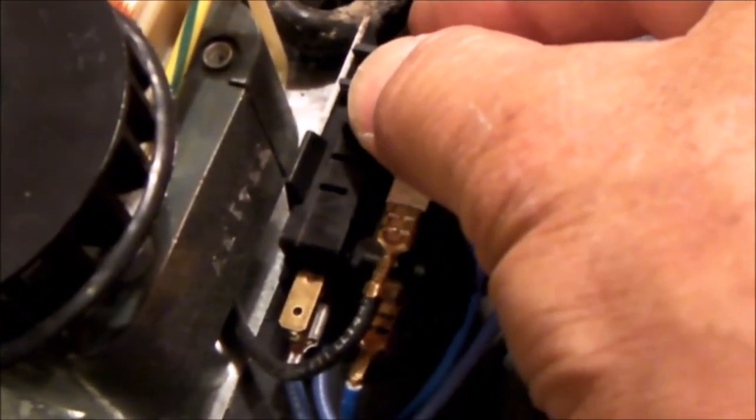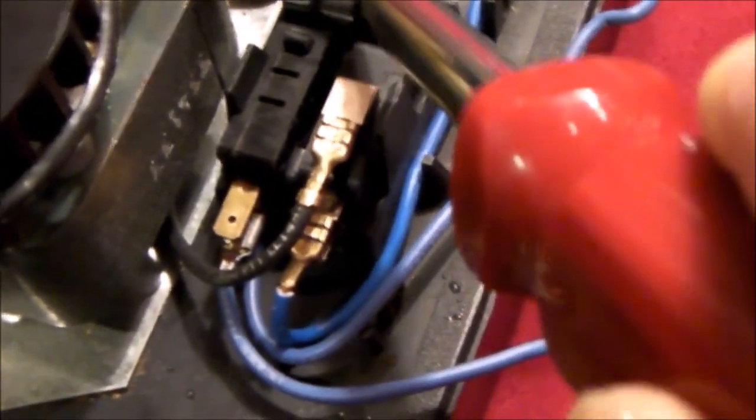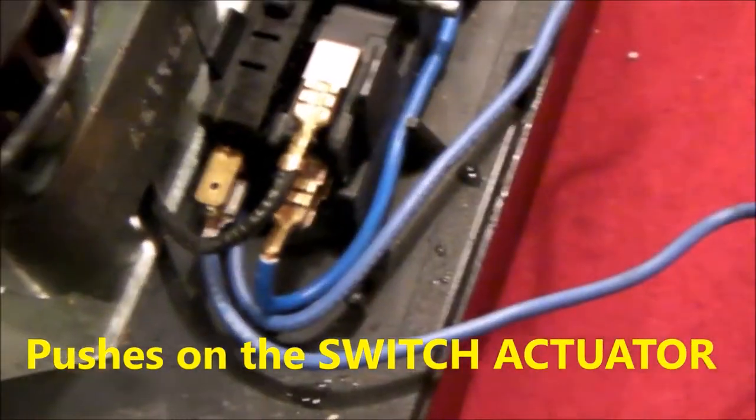So when the float rises up, you'll hear it gets to the top. This actuator arm right here pushes on this contact right here, closes the circuit. Because it was normally open, when the water gets too high it closes, and that turns on my alarm.